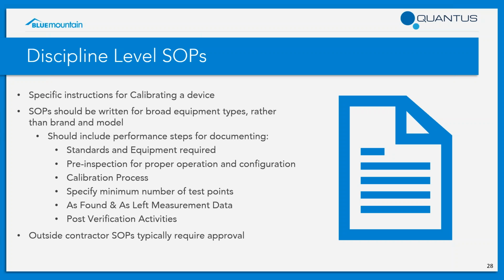That could really balloon the number of SOPs in your program and create a really difficult training environment when you're bringing in new employees. Each SOP should really include items such as standards, equipment and materials that are required, setup and pre-inspection requirements, what type of calibration process should be carried out for that particular type of instrument, the number of test points you're doing, how you handle as found, as left measurements, and then post-verification activities such as review of data, labeling requirements, and how you're going to return these instruments back to service so the manufacturing team can utilize them.